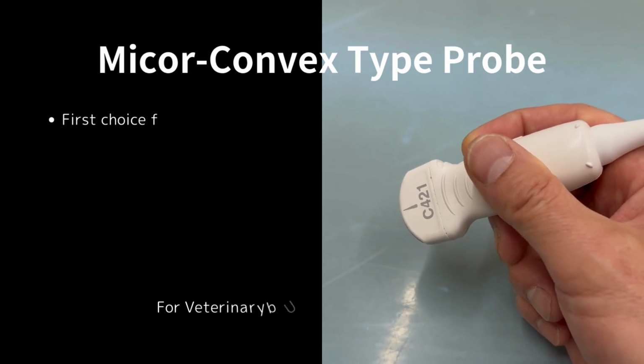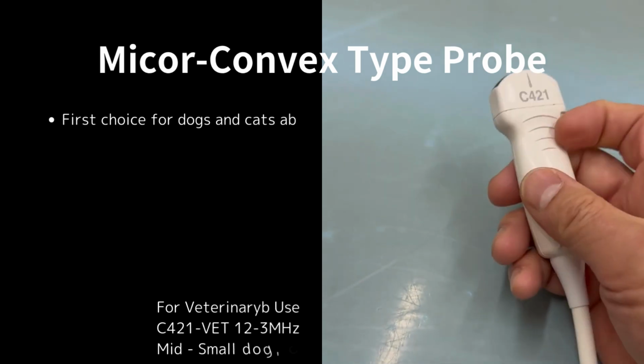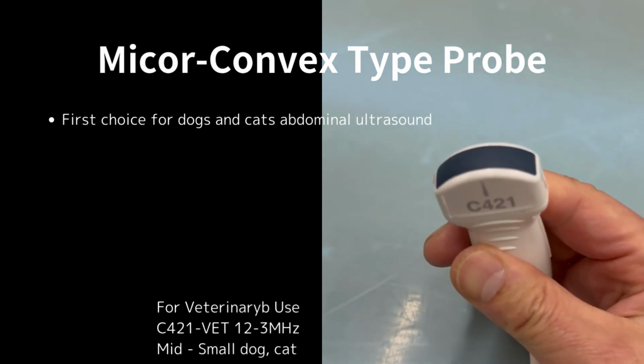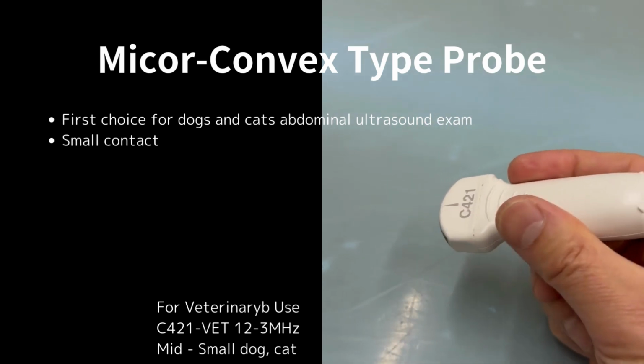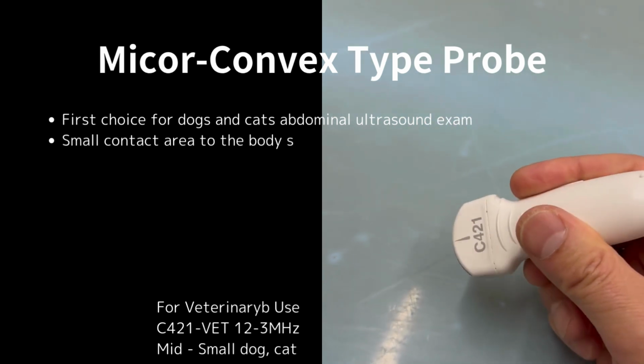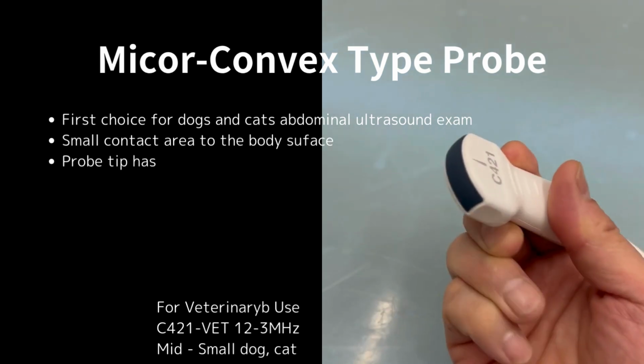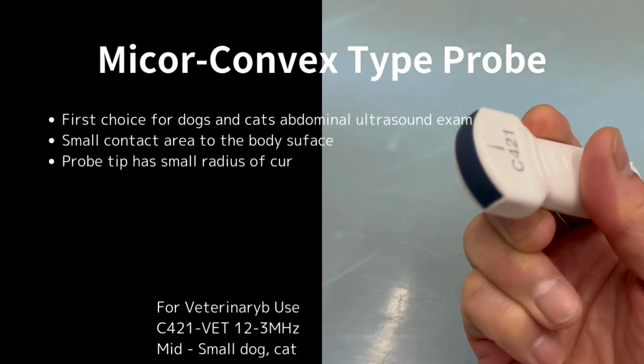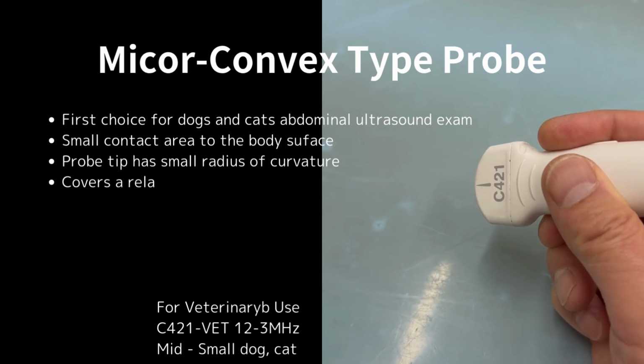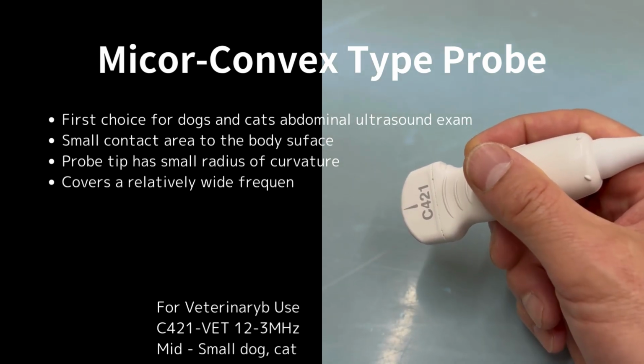First, let's talk about the microconvex probe. This is generally the first choice probe for abdominal ultrasound in dogs and cats. Its main features include a small footprint that contacts the patient's body, a tight curve at the tip for better maneuverability, and a frequency range that typically covers both low and high frequencies.